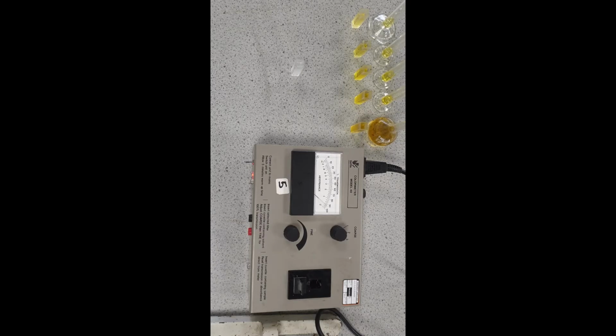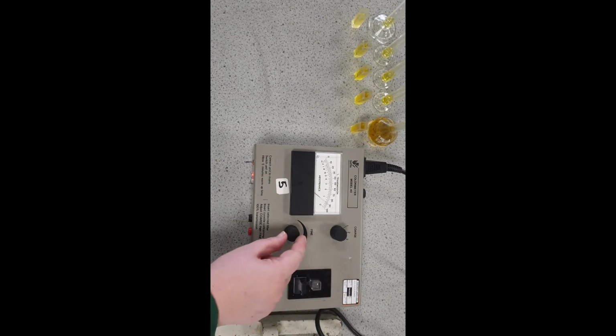Now I need to calibrate it. I get a clean cuvette with some distilled water in and I put it into the colorimeter. Using the fine tuning knob, I make sure that the transmission sits at 100%. This is now ready for use.